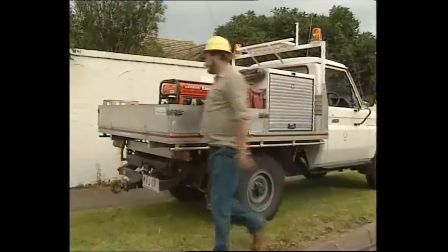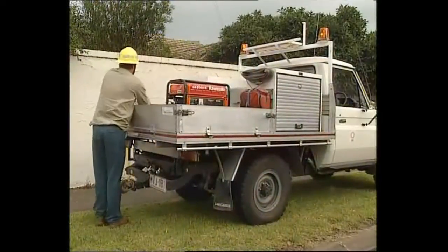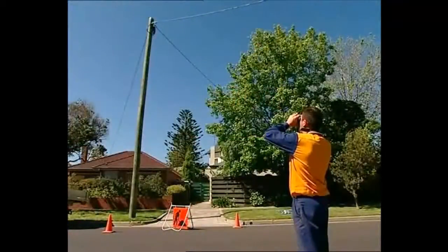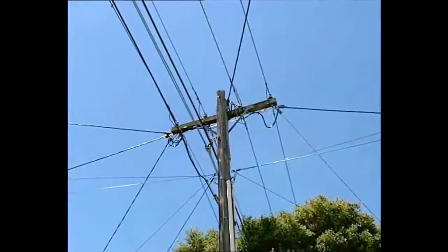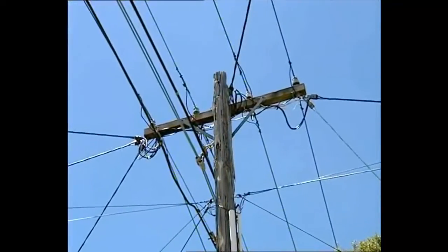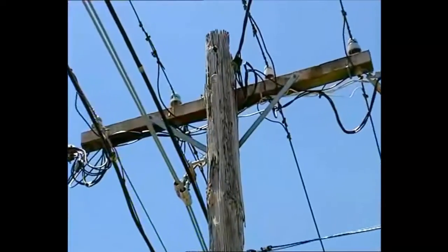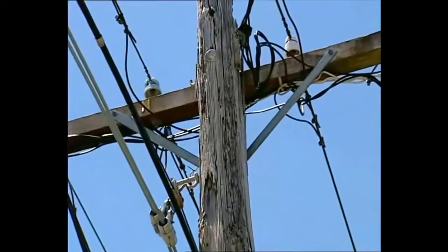Inspection is best done on a cyclic basis of somewhere between 4 and 10 years. This ground line inspection is often incorporated with other inspection functions such as pole top, vegetation, earthing and conductor clearances. This is where valuable information can be provided to network maintenance planners and the necessary repairs and maintenance programmed.